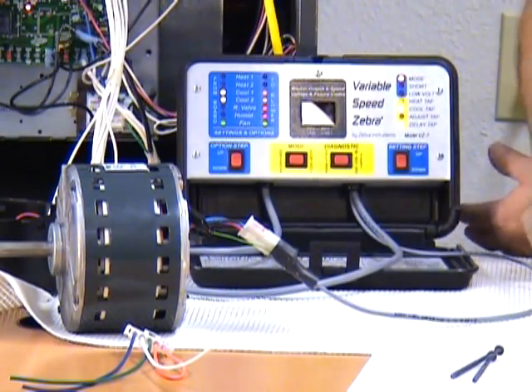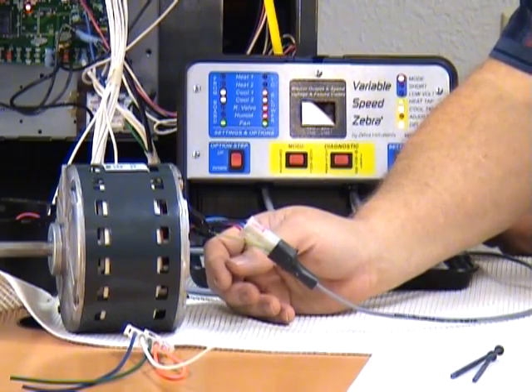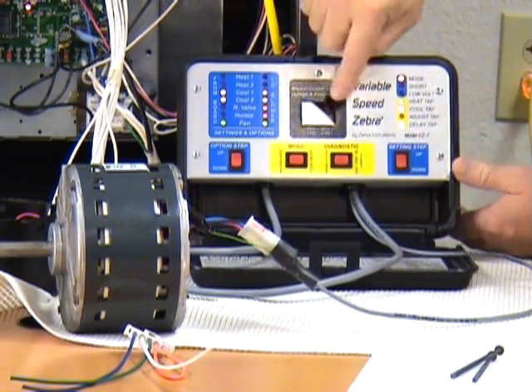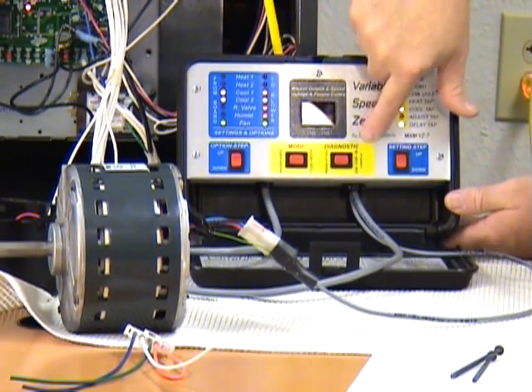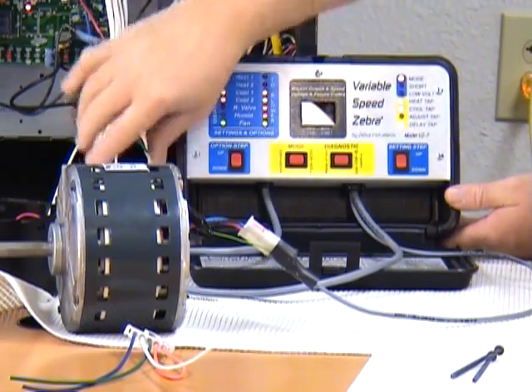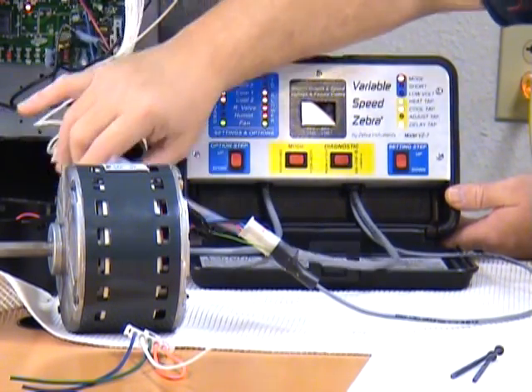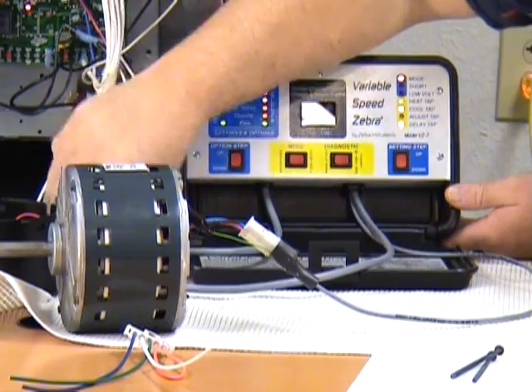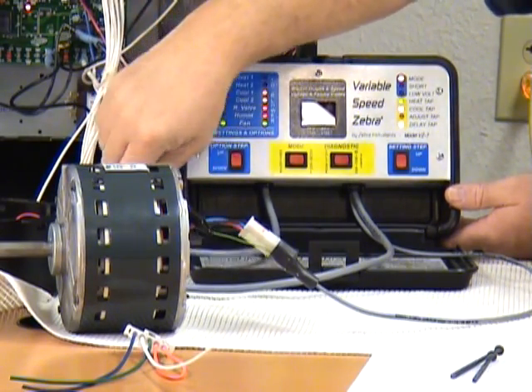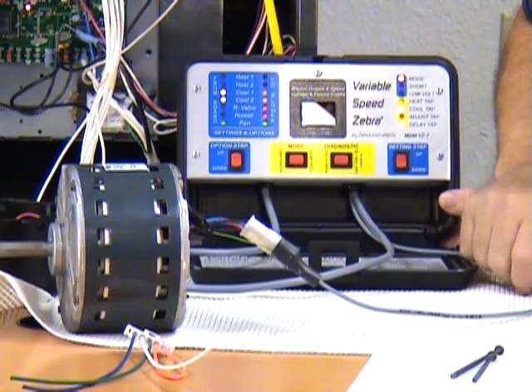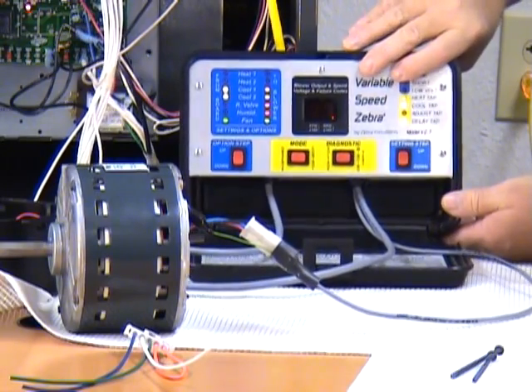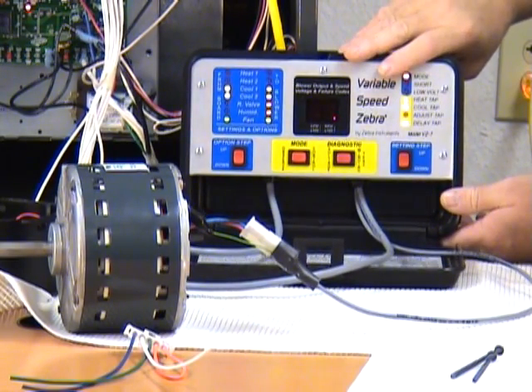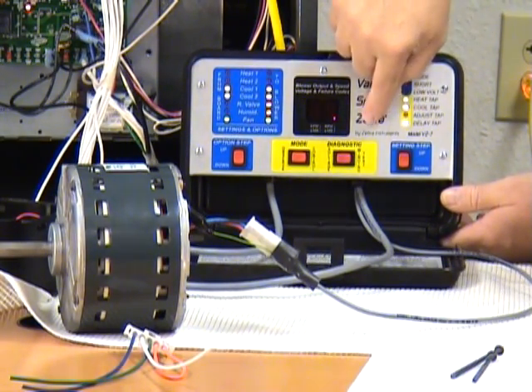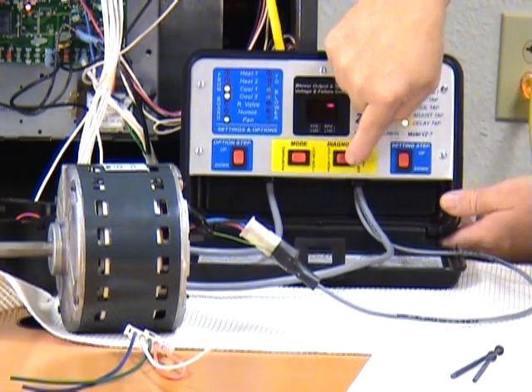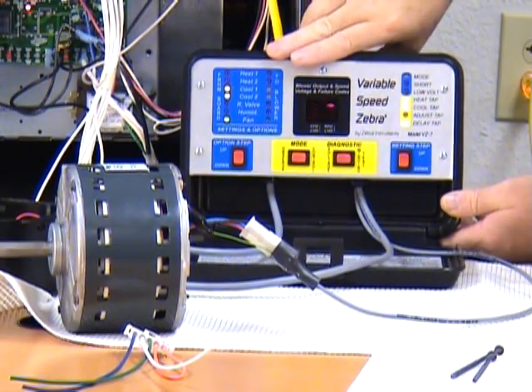So that's what you're going to use our variable speed zebra for now. This is called the winding test. You accomplish that test by having power coming into the variable speed zebra from your furnace board. Your other wire does not have to be connected. The blue harness on your variable speed zebra does not have to be connected to do this test. But you accomplish the winding test by simply pressing and releasing the winding test button.